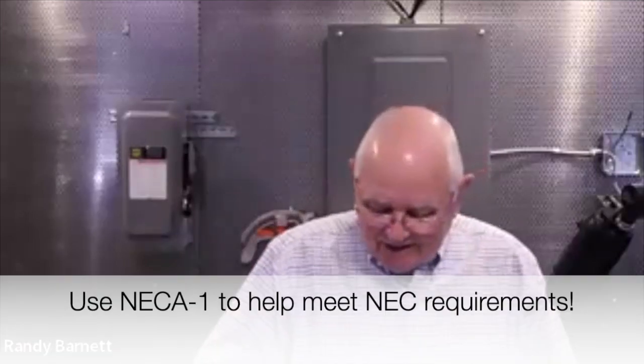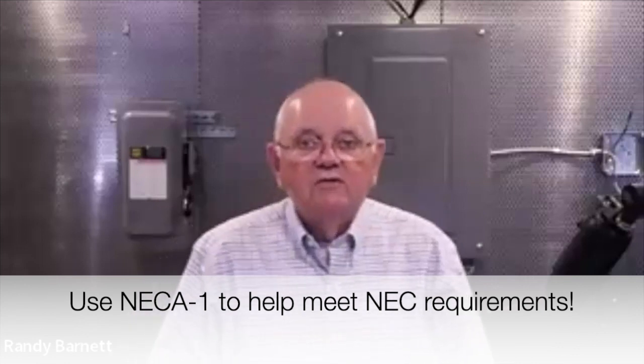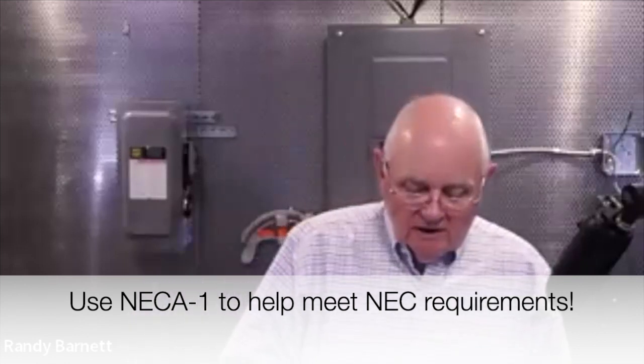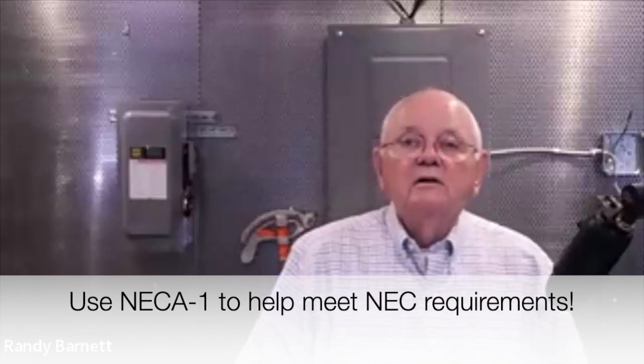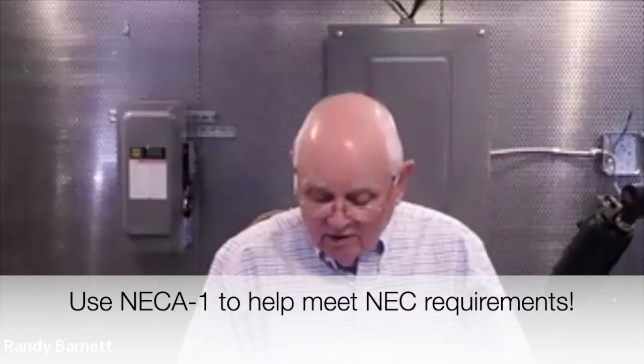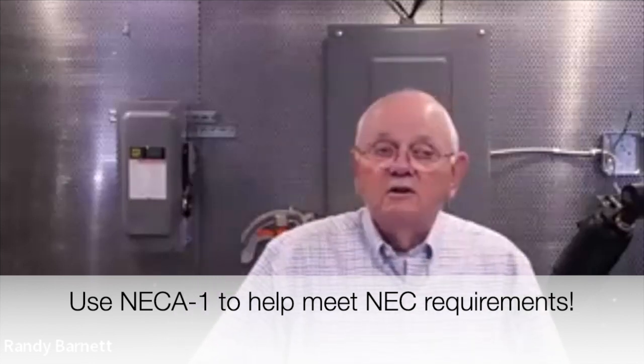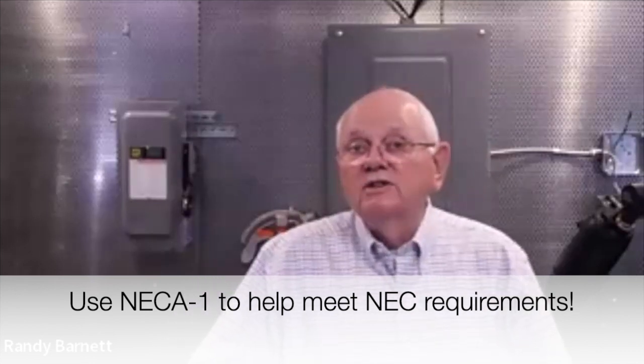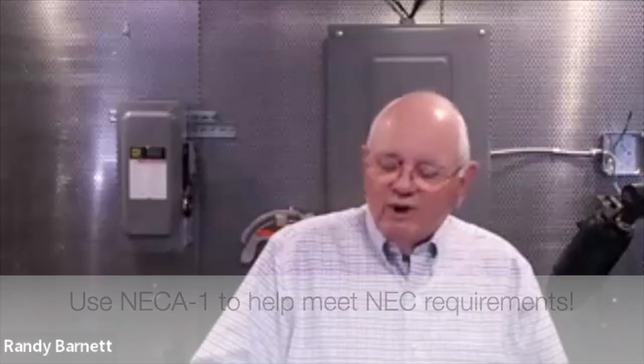And all of a sudden, we got a new pump skid in today, and it's my job to run some rigid and some flex over to that motor and get it all hooked up and ready to go and all of that. So it may be requirements that I'm not familiar with simply because, as I always say, use it or lose it, right? So if I haven't done it in a while, I'll start to forget, especially when it comes to bending conduit, right? So anyway, this standard becomes really good for us, this NECA 1 standard, for not just new construction, but for anybody who does installation type work, whether it's dwelling units, residential, in other words, or other than dwelling units, manufacturing, industrial, pipelines, wherever it is, wherever you're working.